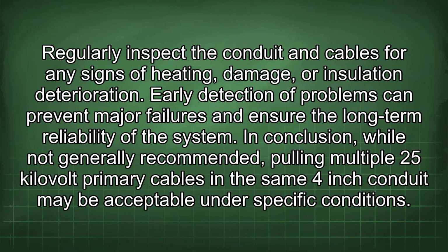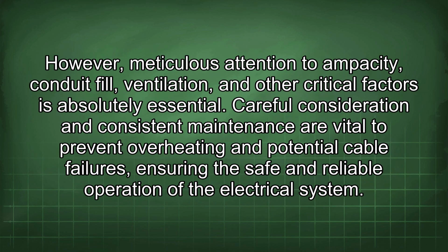Regular inspection. Regularly inspect the conduit and cables for any signs of heating, damage, or insulation deterioration. Early detection of problems can prevent major failures and ensure the long-term reliability of the system. In conclusion, while not generally recommended, pulling multiple 25 kV primary cables in the same 4-inch conduit may be acceptable under specific conditions. However, meticulous attention to ampacity, conduit fill, ventilation, and other critical factors is absolutely essential.